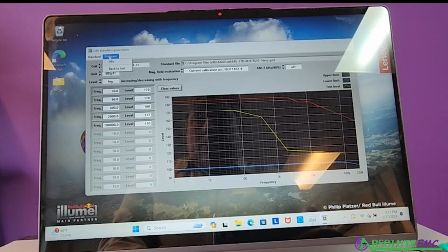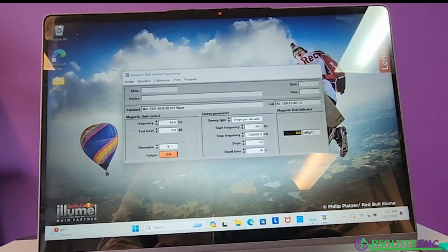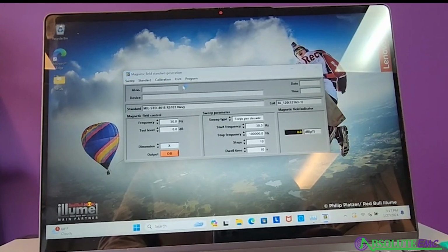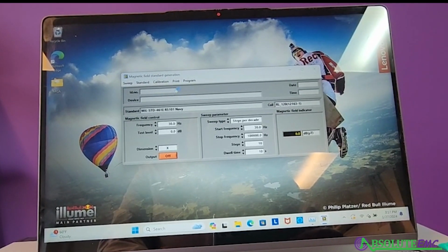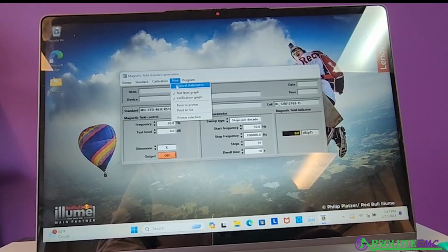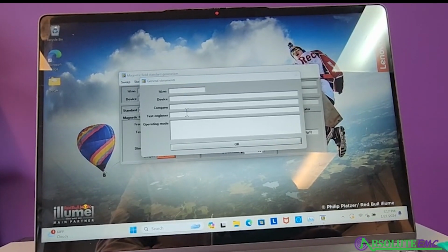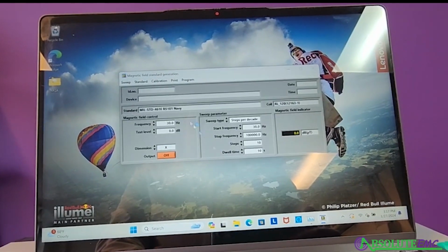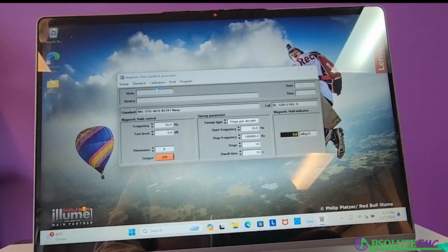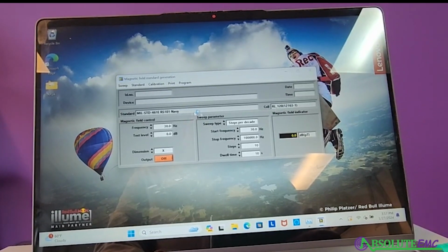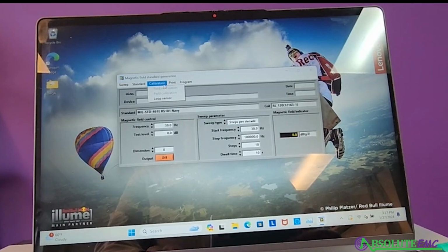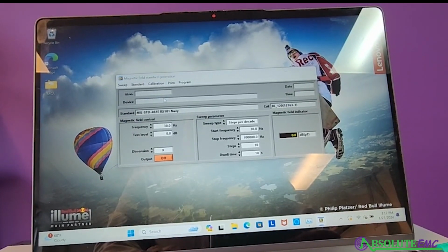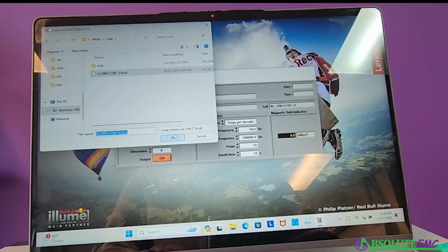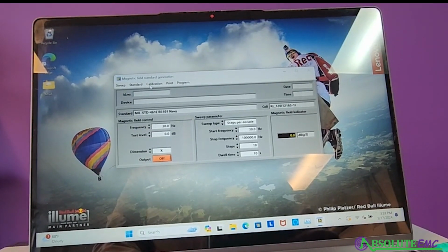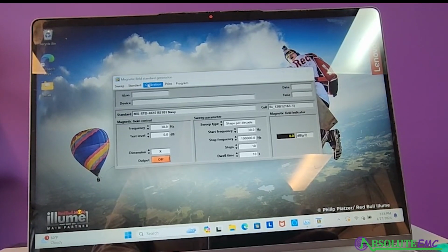So we could save that, or we'll just go back to the test here. So now we're back to the test window. In the test window, we can put in some information about the DUT in the test if we want to, which basically just goes into a general statement here, and we can add our own statements in there. The calibration, we pull up the loop sensor that we're going to use, which is the LS040.